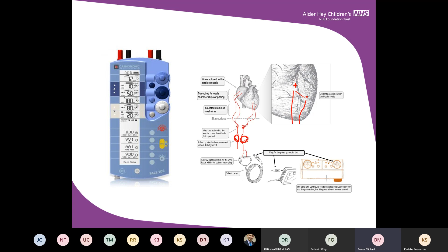You can see that the diagram shows the two leads of the bipolar system 8 to 10 millimeters apart on the ventricle on the inset, but there are also atrial wires, and they come down and are tied together with extra loops to prevent them being accidentally pulled, before being placed into the wire that then goes into the pacing box. And the settings of these devices is probably a whole other session.